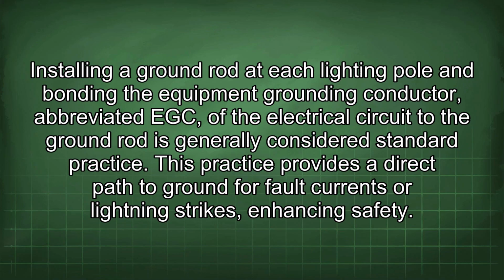Installing a ground rod at each lighting pole and bonding the equipment grounding conductor, abbreviated EGC, of the electrical circuit to the ground rod is generally considered standard practice. This practice provides a direct path to ground for fault currents or lightning strikes, enhancing safety.